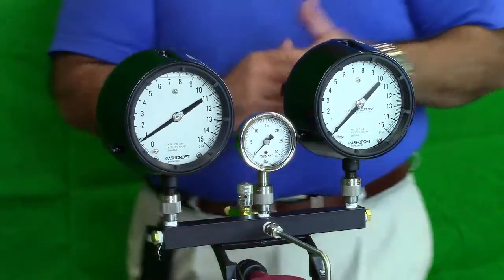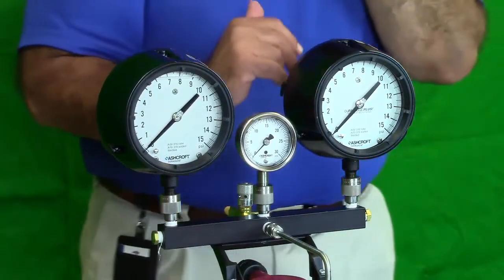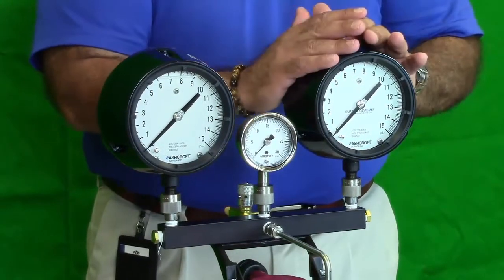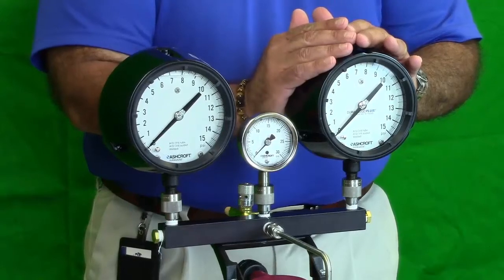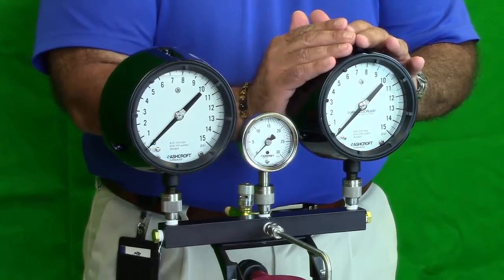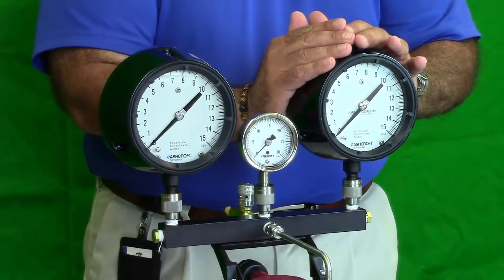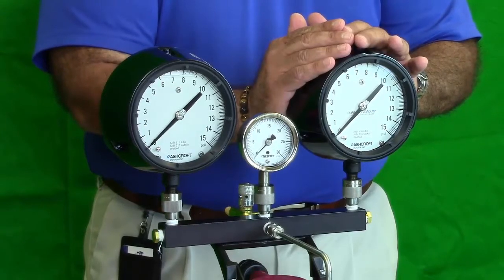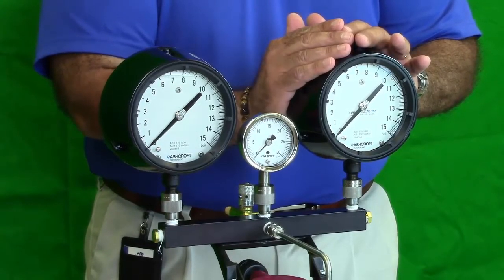Okay, some of the main advantages obviously is reducing and eliminating that vibration eliminates the wear on the Bourdon tube, giving you longer use out of the gauge, allowing you to reduce fills and inventory, having to stock multiple type gauges for various applications.